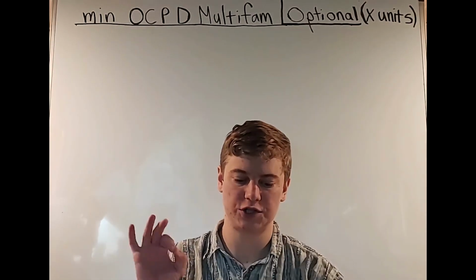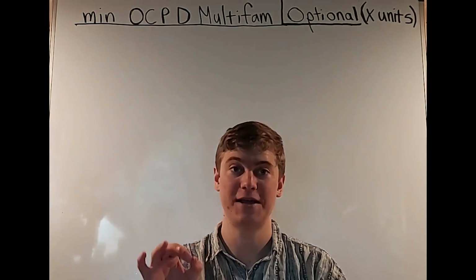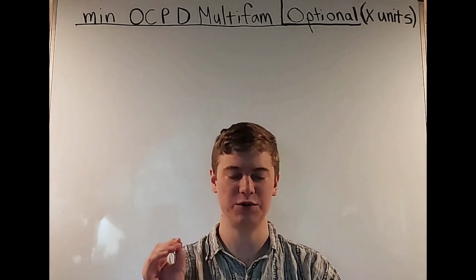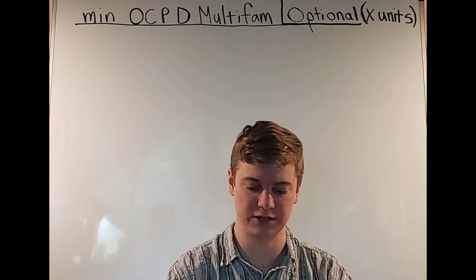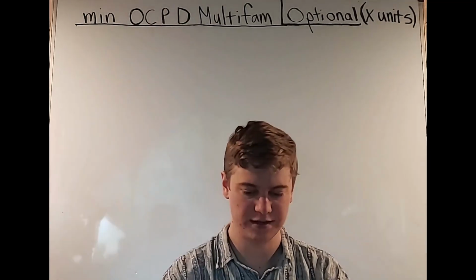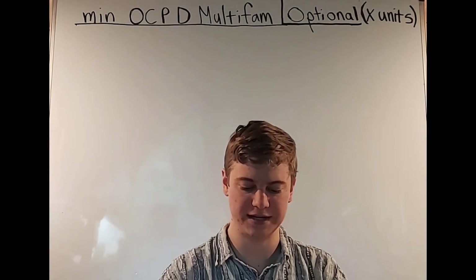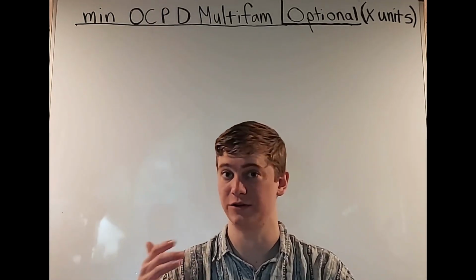Here we see article 220.82 where it says dwelling unit. Pay attention to that. It is not plural, it says dwelling unit. So it's pretty vague, but this is telling you this is only for single family dwellings. In other words, the entire article 220.82, we see section A, B, and C. We were using these when we were doing the optional method for single family dwellings.